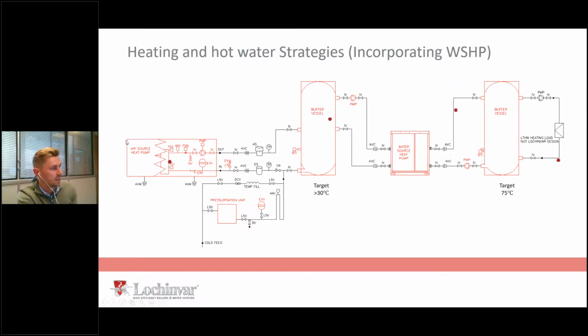So what we have is 1 kilowatt goes into the air source heat pump, 4 kilowatts come out. 1 kilowatt goes into the water source heat pump, 5 kilowatts come out, because we've got an efficiency of 500%, right? So in that circumstance, 2 kilowatts in, 5 kilowatts out, what we've done is we've created a scenario where we're producing water at 70 degrees centigrade, for argument's sake, for a building with an efficiency of 250%.